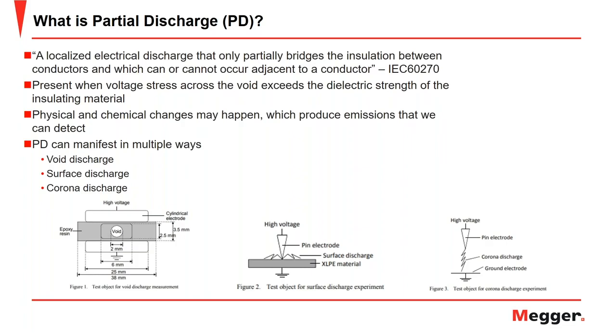When we discuss partial discharge, there are many different ways that PD activity can manifest itself. Here we have 3 primary examples, the first being void discharge. If we take a look at this leftmost figure, you see the solid insulation that has a void in it. The solid insulation has its own dielectric strength, while the void that's filled with air has a separate dielectric strength. It's typically going to be lower than the insulating material around it. So when you apply your electric field, the electric field in that void may exceed that dielectric strength, where it may not have exceeded the dielectric strength in the solid insulating material here. And this will cause that void stress to grow, and then ultimately could cause breakdown between the 2 electrodes.